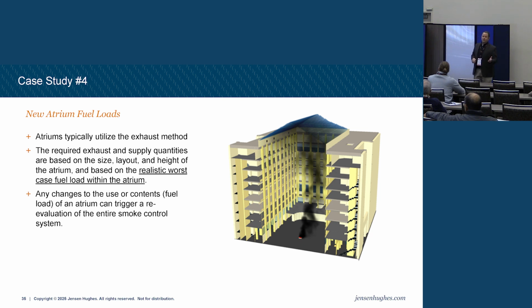Okay, it's all metal with an aluminum benching on it. It looks pretty, it's kind of Art Deco and modern, right? No fire load for me. So from a fire protection engineering standpoint, I'm like, ooh, I like that furniture. But the Starbucks is, you know, an X megawatt or X kilowatt fire. That all goes into the design analysis, and that helps us come up with how much airflow we need.